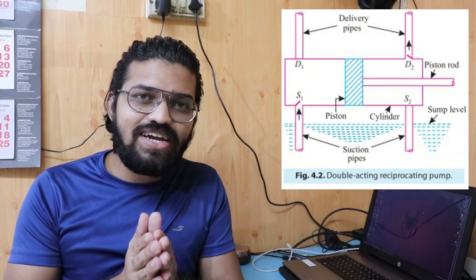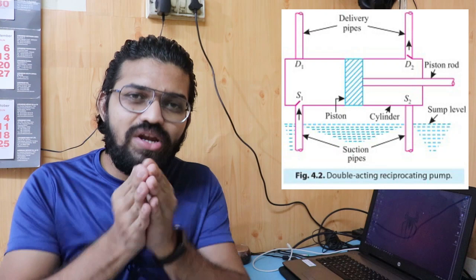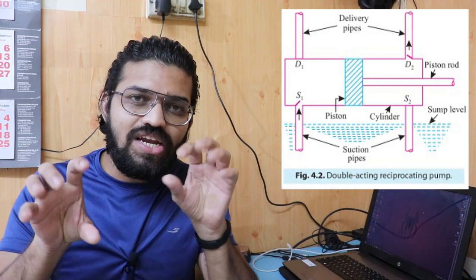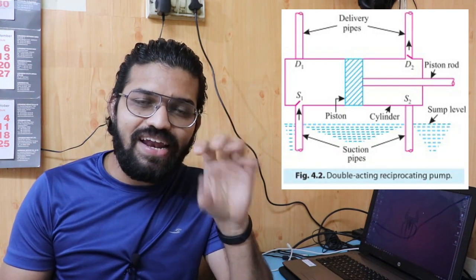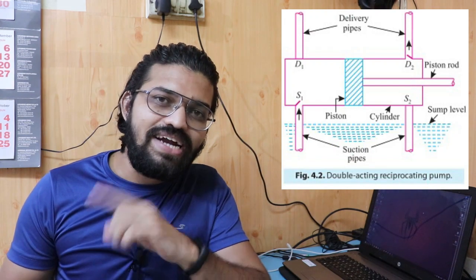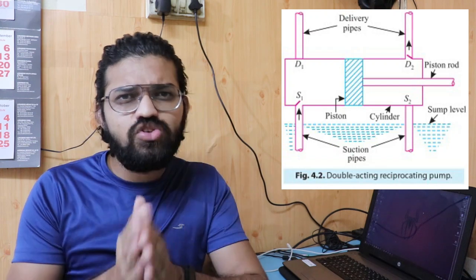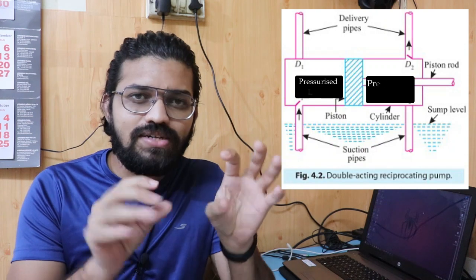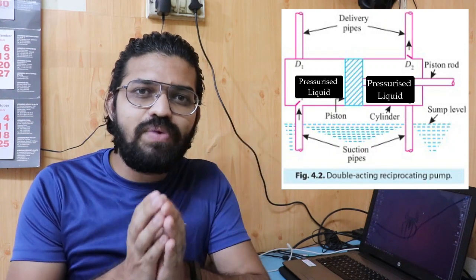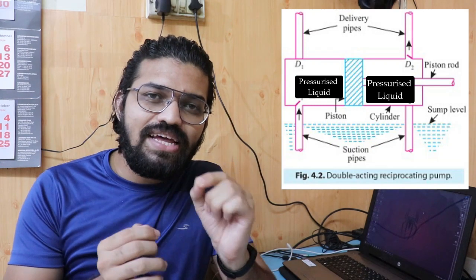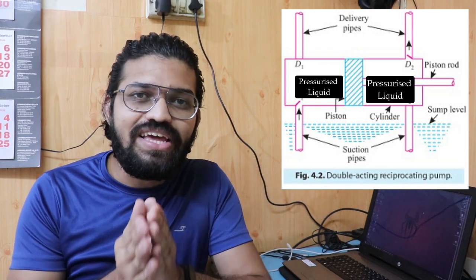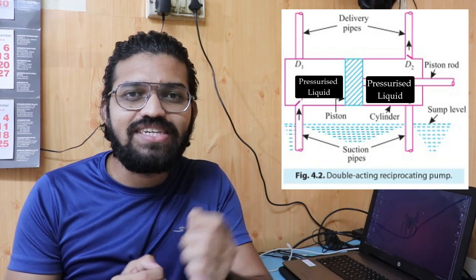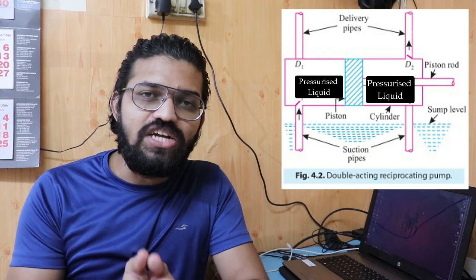Now let's discuss some problems with the double acting reciprocating pump. The piston is the only dividing medium between the liquid on both sides — liquid is present on the left side and also on the right side simultaneously. At a certain point, when liquid is present on both sides of the piston, there is a chance of leakage, which is termed as slip.